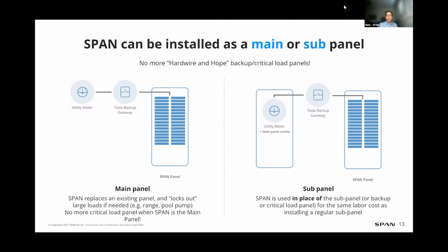I'll show in some upcoming slides some of the costs that you have to incur anyway - you have to wire up a backup load panel or load shedding device - it then offsets some of the cost of doing SPAN. The customer gets so much more, whether it's a main or a sub panel. So in many cases, we're seeing people include these with battery systems as standard, or simply offering them on main panel upgrades whenever those are required as well.